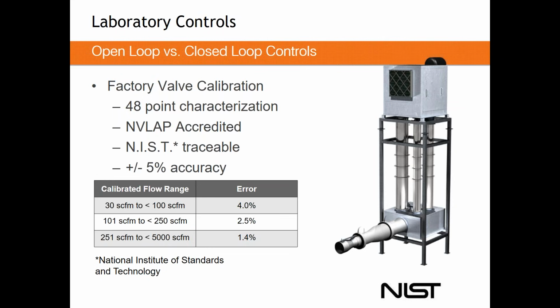So basically the airflow rig will push some air through it and measure that itself and then record the position the Venturi valve's at. That's a 48-point test. Automated and working properly, that takes 12 to 15 minutes per Venturi valve, so long as no part fails or it's not out of calibration or something like that. So it's a highly labor-intensive portion of the Venturi valve creation, this test.